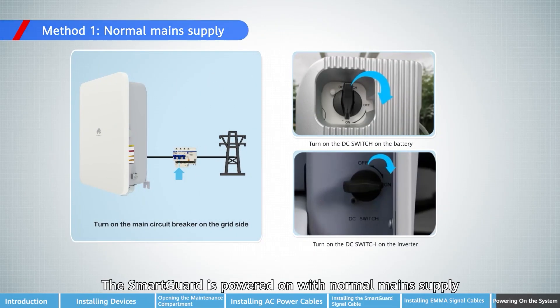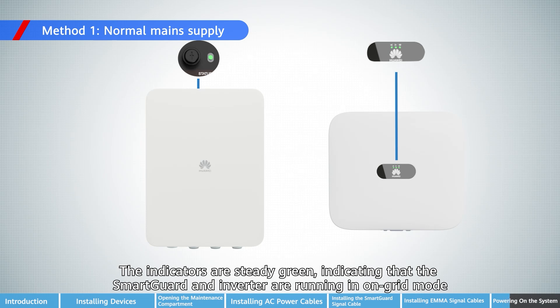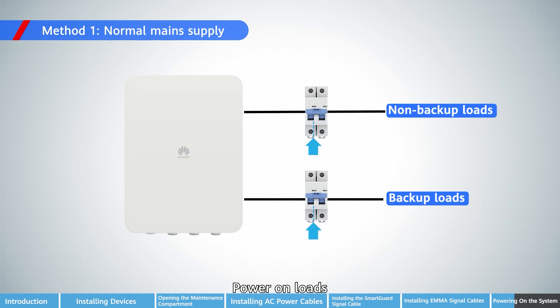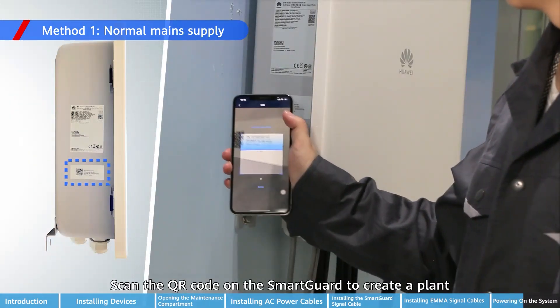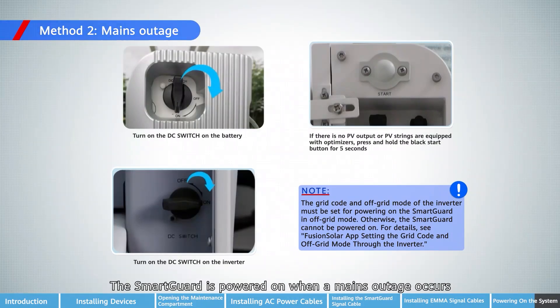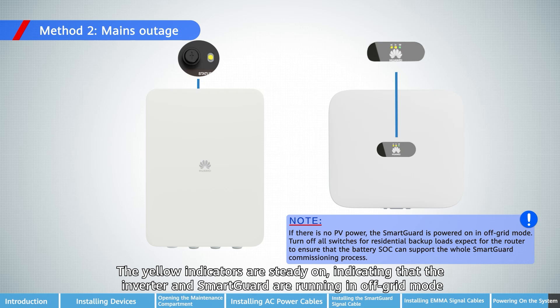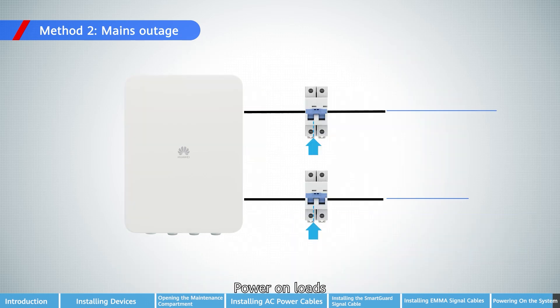The SmartGuard is powered on with normal mains supply. The indicators are steady green, indicating that the SmartGuard and inverter are running in on-grid mode. Power on loads. Scan the QR code on the SmartGuard to create a plant. When a mains outage occurs, the yellow indicators are steady on, indicating that the inverter and SmartGuard are running in off-grid mode.